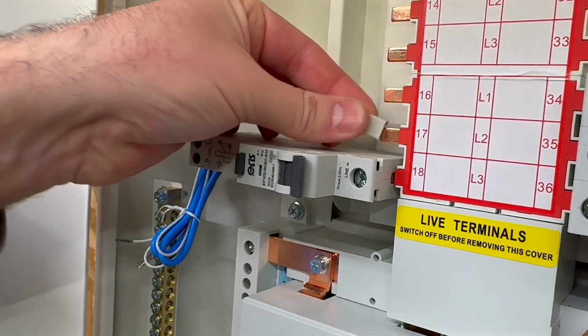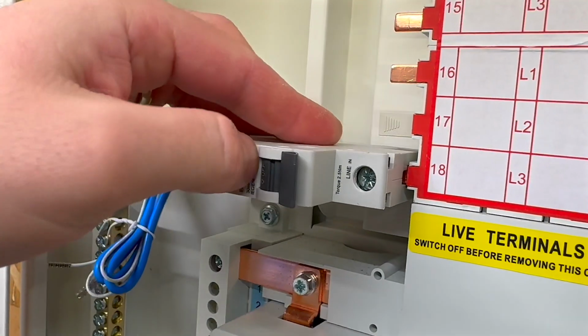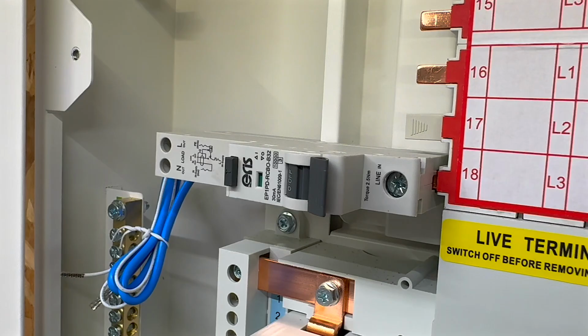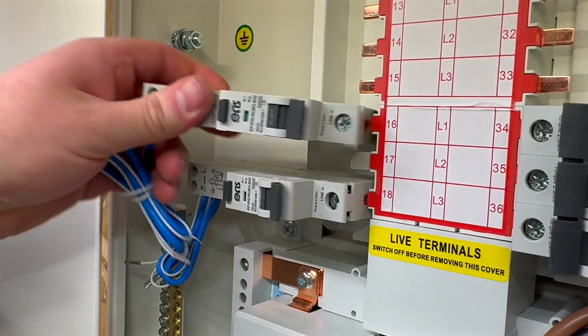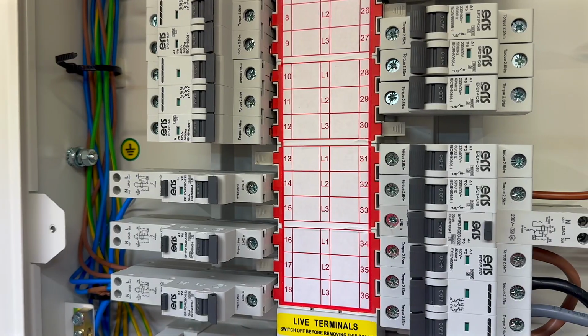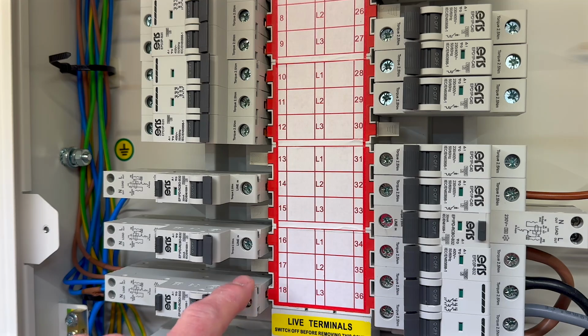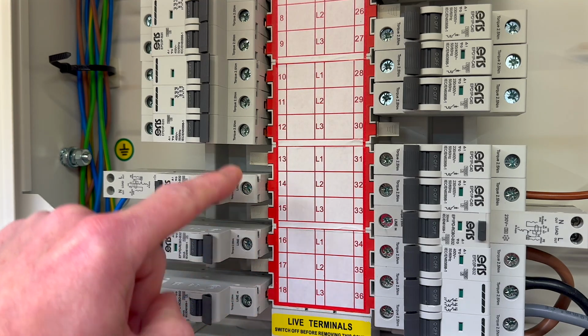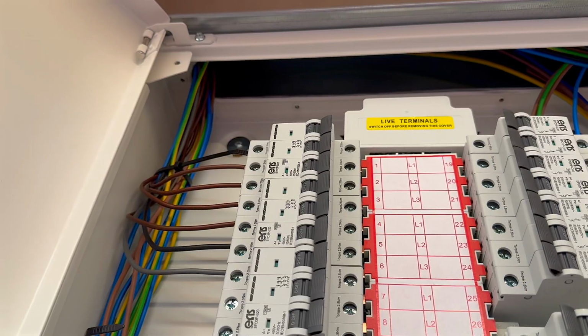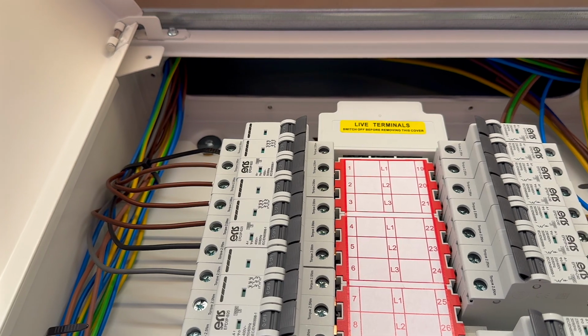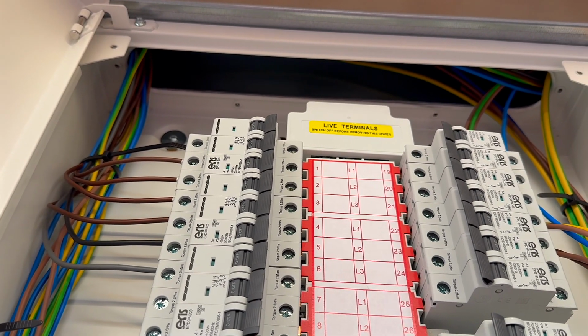At a minimum, any unused slots in the board should be covered with insulating caps to ensure all live parts meet the IP2X standard for fingerproof safety. Similarly, covers must also be fingerproof once replaced, which means blanks must be fitted to any unused slots. Additionally, the top surface must comply with IP4X or IPXXD standards as outlined.